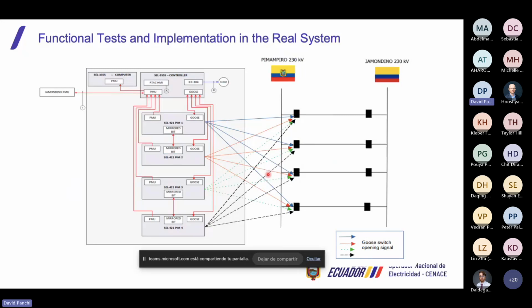So the last step of this project is the implementation in the real system. Once we have tested in the digital twin system and the results were good, we proceed to implement this scheme in the real system. So how do we do that? In order to provide the ability to observe what is happening in the interconnection at any time and monitor the actual behavior of the system, an automation equipment was implemented in the substation in Ecuador that allows detecting each program logic here.